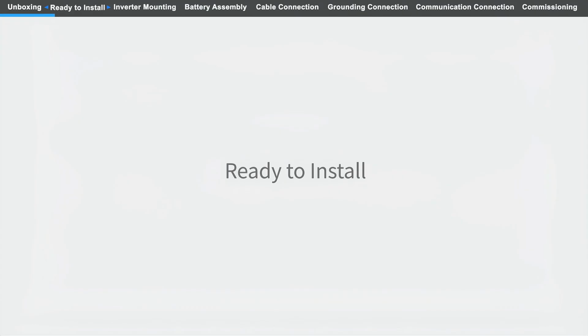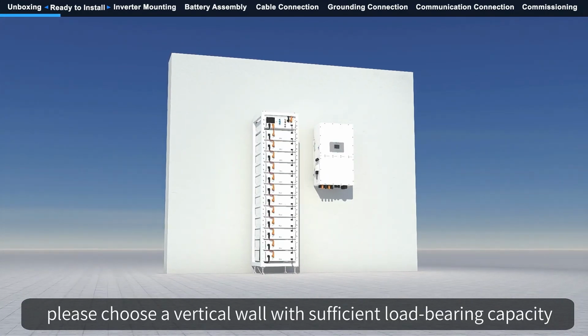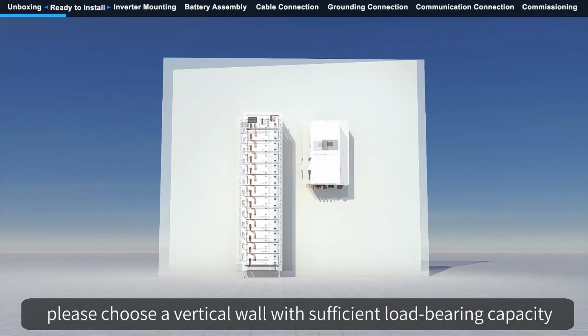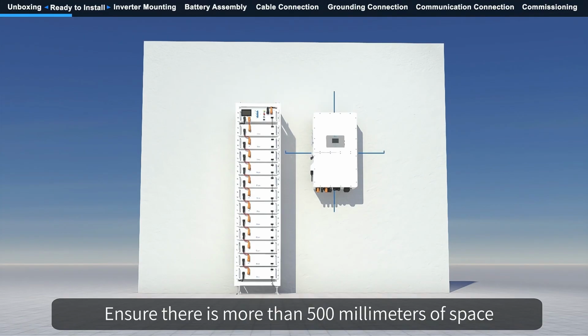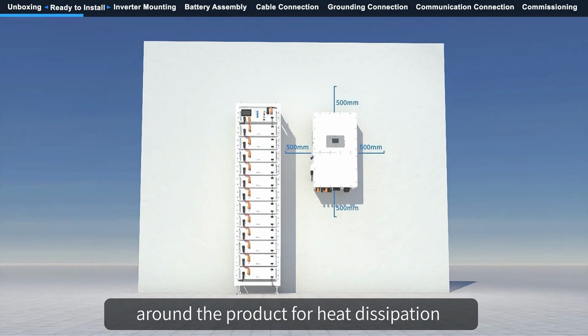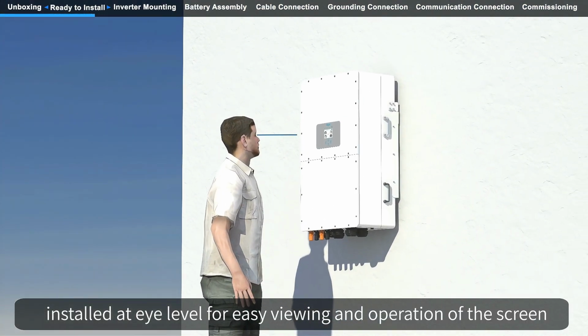Ready to install. When installing, please choose a vertical wall with sufficient load-bearing capacity. Ensure there is more than 500 millimeters of space around the product for heat dissipation. It is recommended that the inverter be installed at eye level for easy viewing and operation of the screen.